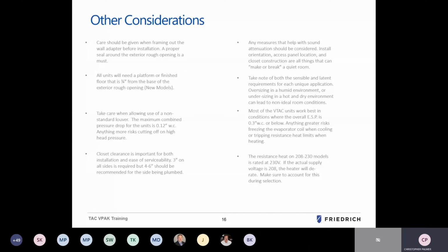Take note that both the sensible and latent requirements of each unit are unique to the application. Oversizing in a humid environment or undersizing in a hot, dry environment can lead to non-ideal room conditions. Equipment size and our heat load calculations are critical in choosing which equipment we want to use in the application.